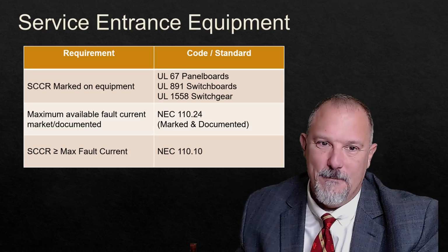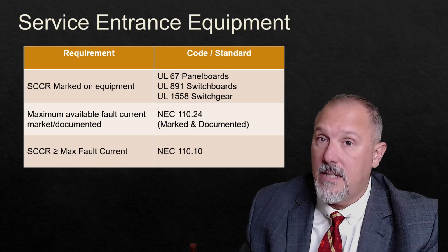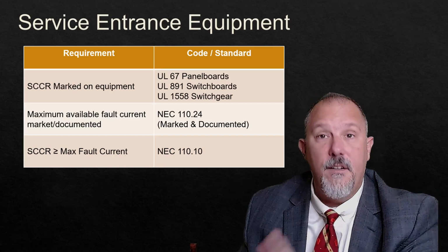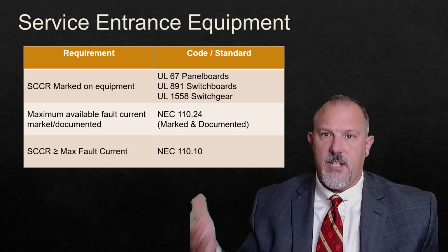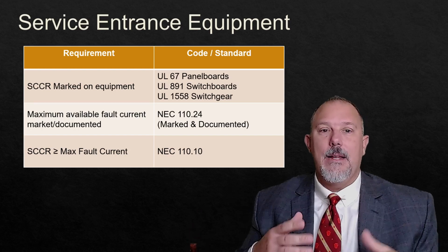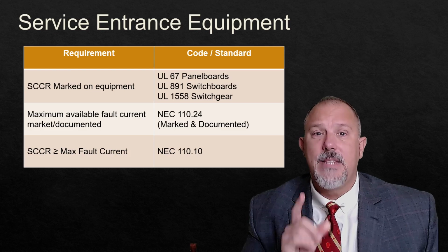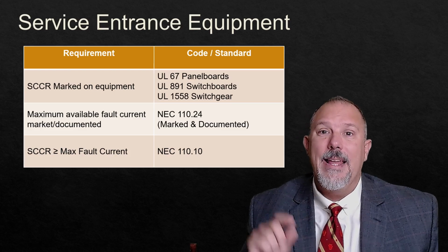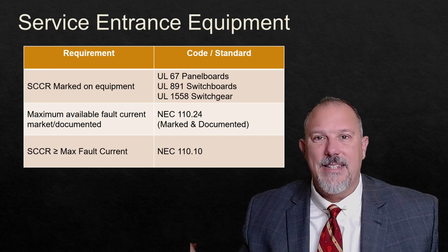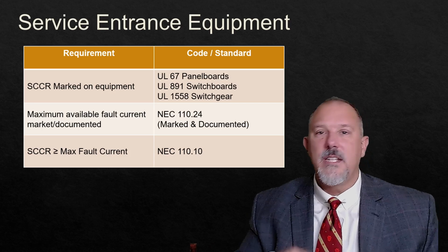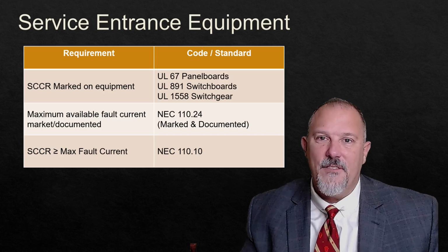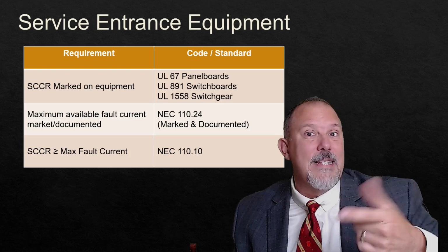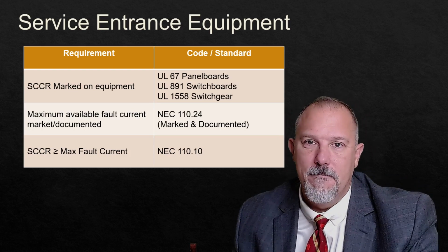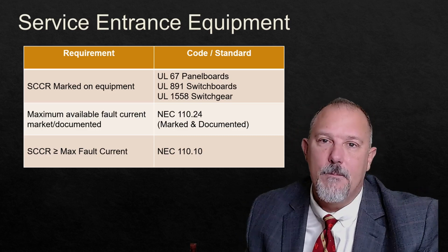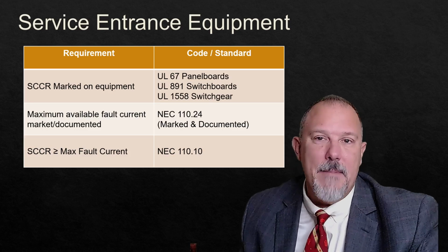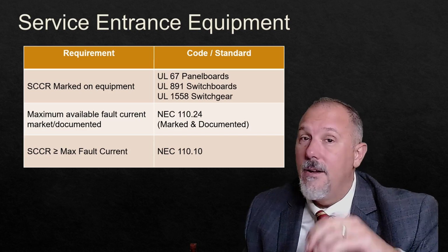let me help you understand my philosophy here. What a panel board is marked with is the recipe to determine the short circuit current rating of that equipment, because it doesn't say the short circuit current rating of this equipment is 65K, 100K, or 200K. What you will typically see on a panel board is that the short circuit current rating of that equipment is based upon the lowest interrupting rating device that's installed inside. So if I put all 65K circuit breakers in a panel board, it is a 65K short circuit current rating. If I take one of those breakers out, or let's say I'm going to add a circuit to that panel board, and I go to the supply house, I say, hey, I need a 60 amp three pole breaker to fit in an XYZ manufacturer catalog number LMNOP panel board.